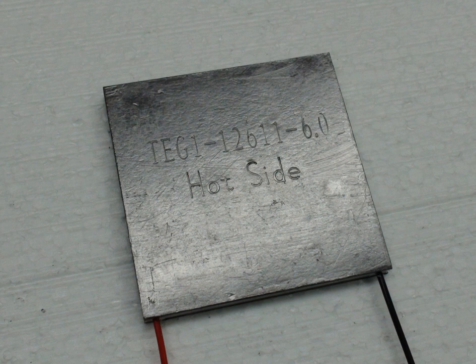One of the most significant benefits of TEC systems is that they have no moving parts. This lack of mechanical wear increases the lifespan of the system and lowers the maintenance requirement. Current technologies show the mean time between failures (MTBF) to exceed 100,000 hours at ambient temperatures. Additionally, concerns such as fatigue and fracture become far less applicable to a stationary system.